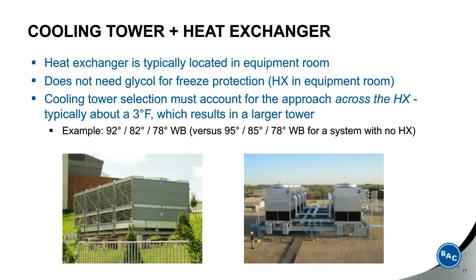Now, the heat exchanger is typically located in the equipment room, which means that the equipment room needs to be larger, which reduces the rentable area in the building. So that should be taken into account. Because the heat exchanger is in the equipment room, however, you do not need glycol for freeze protection, although you should follow the proper cold weather operation procedures for the open circuit cooling tower when you're operating during the winter months. And here's an important point, in that the cooling tower selection is different than the traditional open loop system.